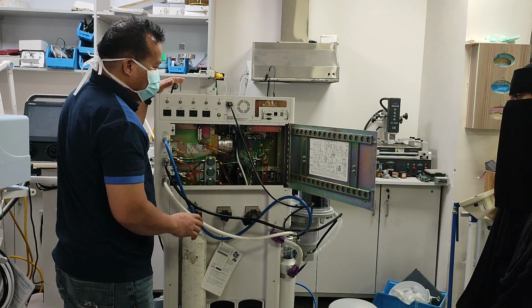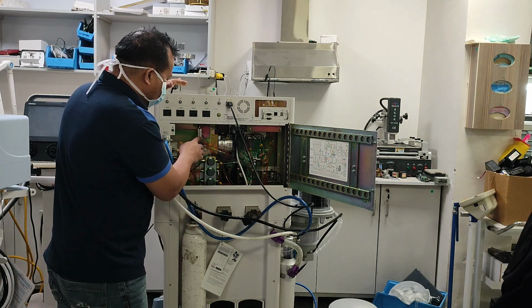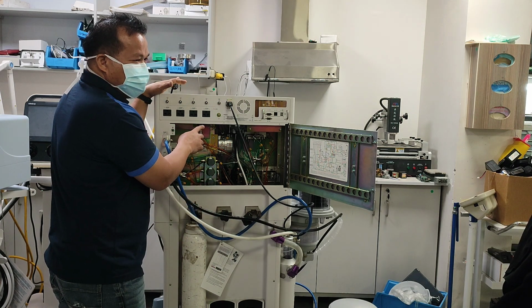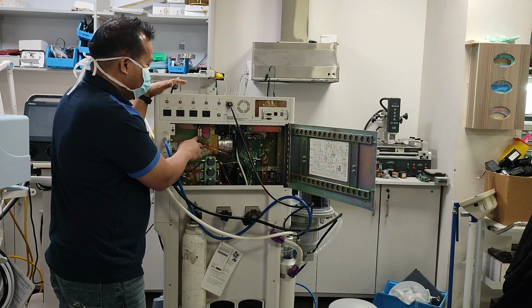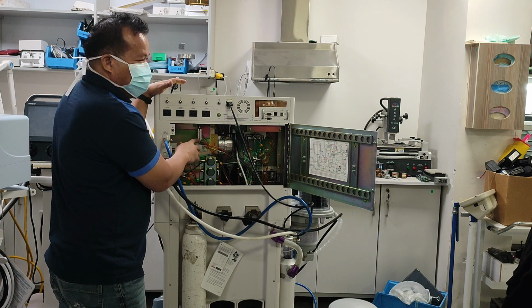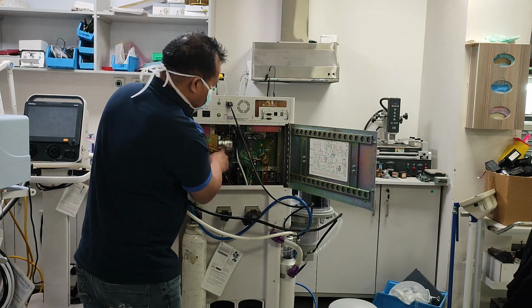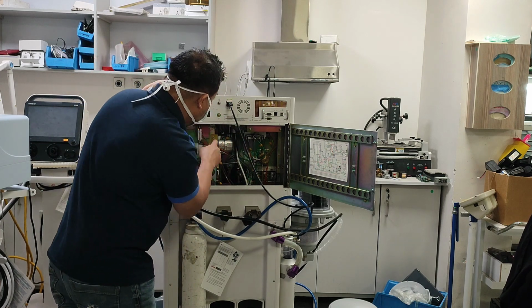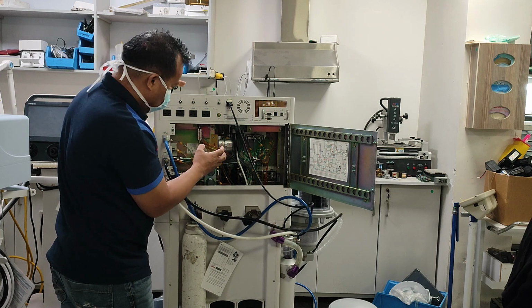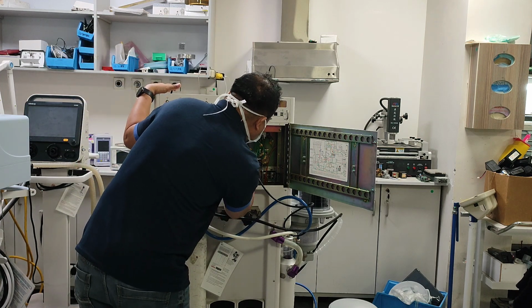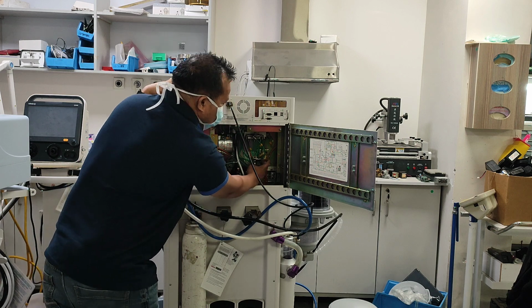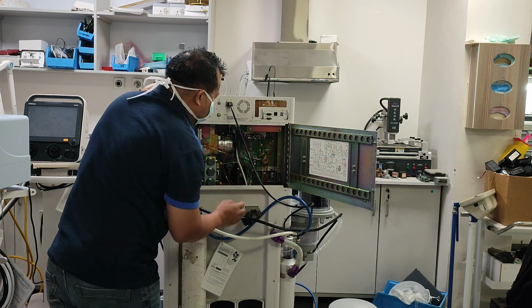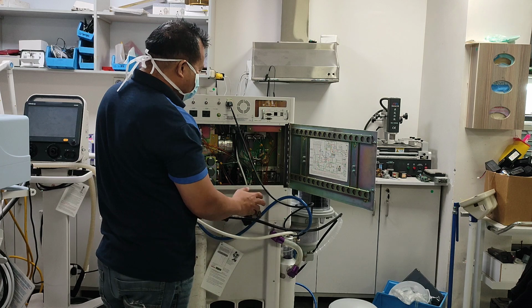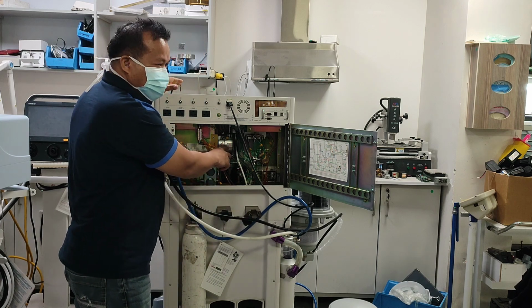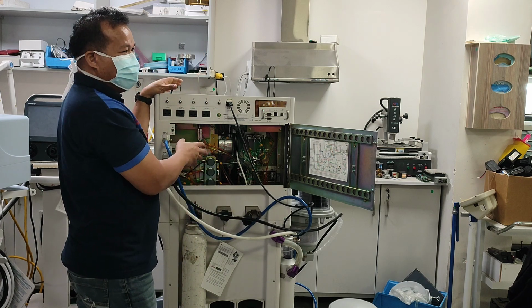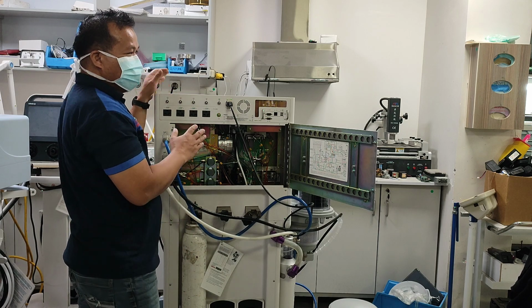If you are a service engineer and you see this, just keep in mind that you should not touch or rotate it, because it was calibrated. The screws marked like this were calibrated at that pressure. If you see the other ones, the nuts have no Loctite, so you can adjust them without any harm. But if you touch this one, it will harm the machine. Maybe the calibration will no longer be accurate.